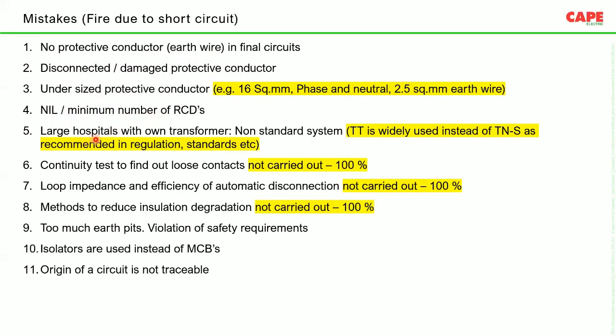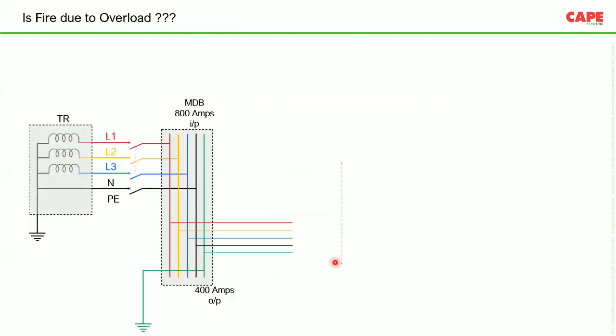The RCDs are not there. A large hospital with its own transformer has non-standard system earthing. TT is widely used instead of TN-S as recommended in regulations and standards. Continuity tests to find loose contacts are not carried out, unfortunately 100%. Fault loop impedance testing is not carried out 100%. Methods to reduce insulation degradation are not carried out. Too many earth pits, a violation of safety requirements. Isolators are used instead of MCBs. The origin of a circuit is not traceable. These are some of the issues which we find.